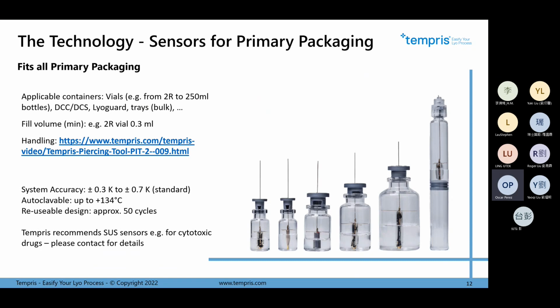The accuracy of the sensors we talked about already is plus minus 0.7 Kelvin as standard, and we can offer more accurate up to 0.3 for the complete system - it's important to mention this applies not only to the sensors. The sensors can also be cleaned and sterilized, and all this information is specified in the product data sheet.